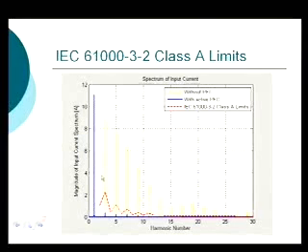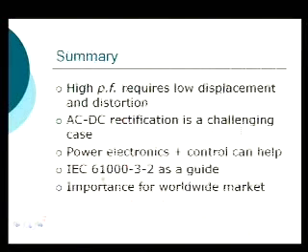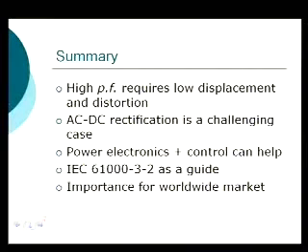This is not particularly important in the U.S., where as far as I know there are no strict limits on input current harmonics at these low levels. But the IEC is an international set of limits, so if you want to market this worldwide, it's a good idea to meet them. You add a little expense with this converter and control, but then you can sell to a whole worldwide market and may end up benefiting.